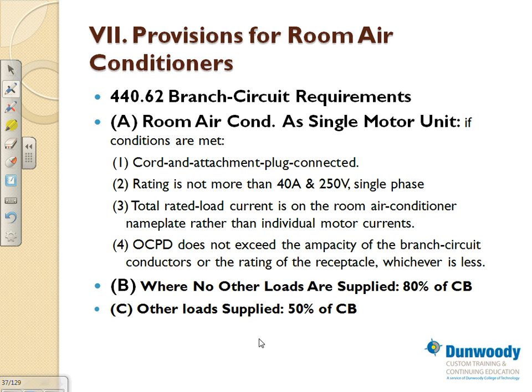Do you see a three-phase chiller here? Where you can plug a three-phase chiller? The limitation is single phase. Look at the limitation of the amps and the voltage, guys. You can't go higher than these voltages and these amps. The total rated current on the air conditioner nameplate, rather than an individual motor current, is used.